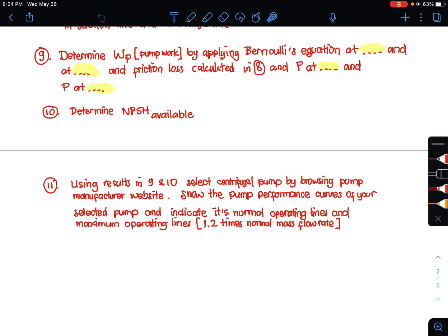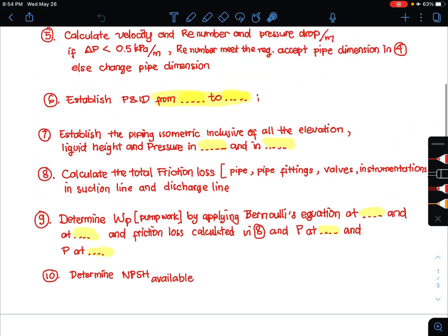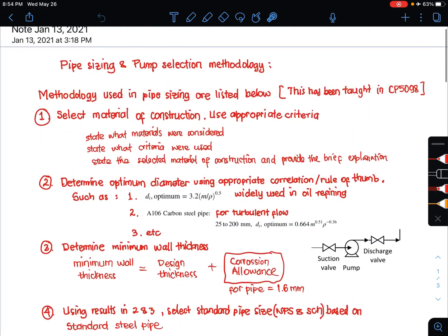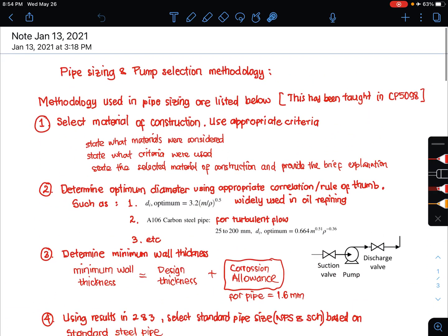You must show the pump performance curves of the selected pump and indicate the normal operating line and the maximum operating line, where the maximum operating flow rate is 1.2 times the normal mass flow rate. This demonstrates that the selected pump can meet both normal and maximum operating conditions. With this overview, I hope you will be able to perform pipe sizing and pump selection. Thank you.